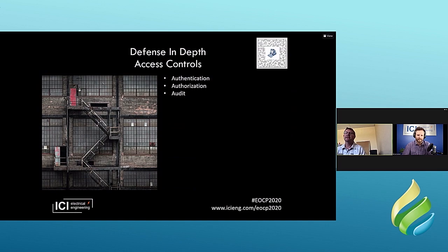But I've had people who say, well, how hard can it be? All he does is push buttons. So he winds up playing with it, doesn't phone anybody out. Next thing you know, he shuts the plant down. Oops. Well, he wants to cover his butt, so he deletes his phone call. And then when you come in the morning, it's like, why is the plant offline? Well, he says, I never got a call. Well, like Sean said, with the auditing portion, there are logs. Any operator can go into the log in their SCADA system and say, oh yeah, it did call out. So you've got to be careful with those things and not just allow anybody to have access to it.